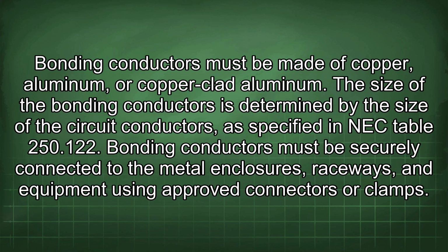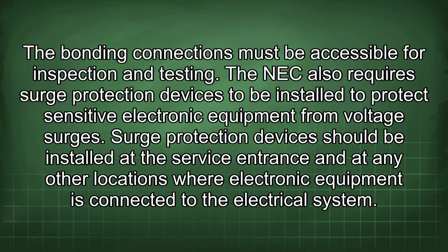Bonding conductors must be made of copper, aluminum, or copper-clad aluminum. The size of the bonding conductors is determined by the size of the circuit conductors, as specified in NEC Table 250.122. Bonding conductors must be securely connected to metal enclosures, raceways, and equipment using approved connectors or clamps. The bonding connections must be accessible for inspection and testing.